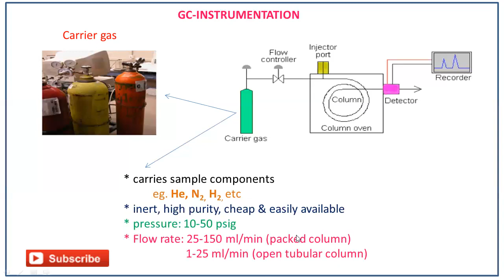And the next component here is the flow controller. This is the flow controller which is present just after the carrier gas, and it controls the flow and the pressure of the carrier gas. It is very essential. Why? Because the carrier gas in the cylinder will be at high pressure. If there is no flow controller, the high pressure will damage the column. So we need to control the pressure of the carrier gas. These flow controllers deliver the gas with a constant flow, and we can check this constant flow in this meter.